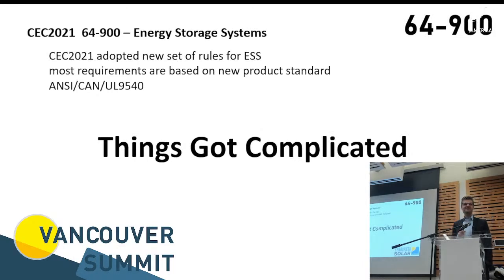And now the most interesting part of the presentation is what effect all of that has on the Canadian market and the code. And it's really complicated. That's the main message, and it's a pain in the butt. If you read the code as it's written right now, you can literally not put any battery storage system in-house. Not possible. But there are some options and some deviations in different provinces where you have some ways around that, so you can still do it, or you don't put it in your dwelling directly. There are some rules that you can actually put it in an attached garage, for example, or detached garage, where the risk to the actual dwelling is a little bit lower.